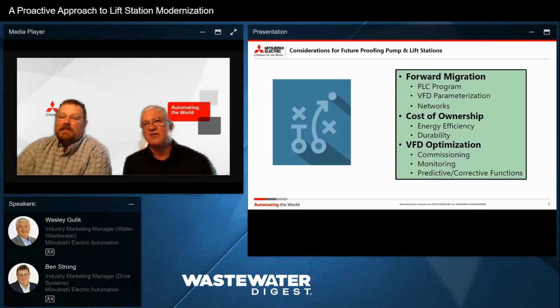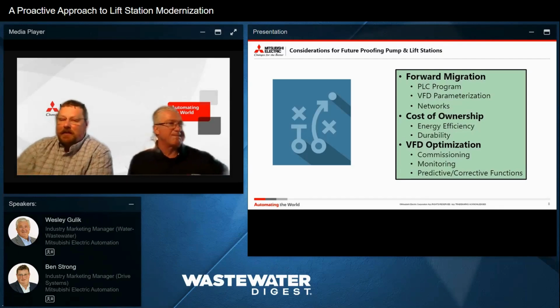The point that I'm trying to make is, when you are evaluating and trying to move forward, first of all, we want to implement variable frequency drives as opposed to soft start. Of the manufacturer you are investigating, ask them, number one, do they manufacture all their VFDs? And are the parameters the same from 30 years ago? There will be some manufacturers, and one specifically comes to mind, whose VFD parameters have been the same for the last 40 years.